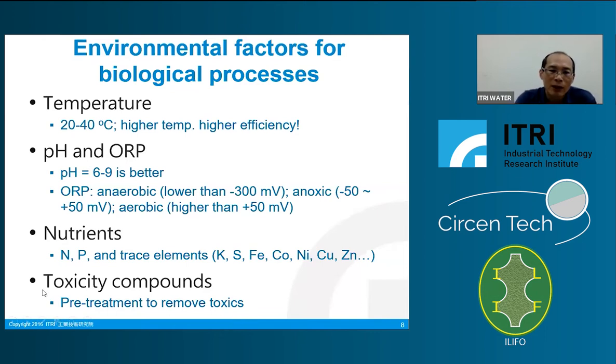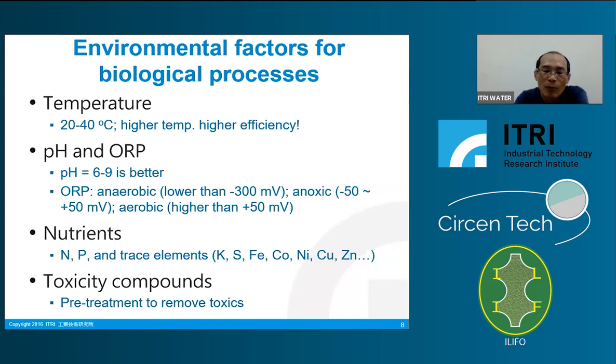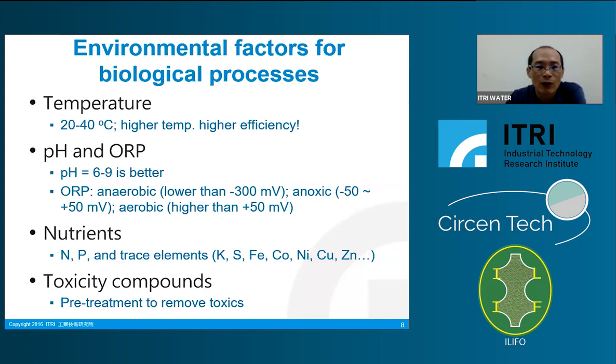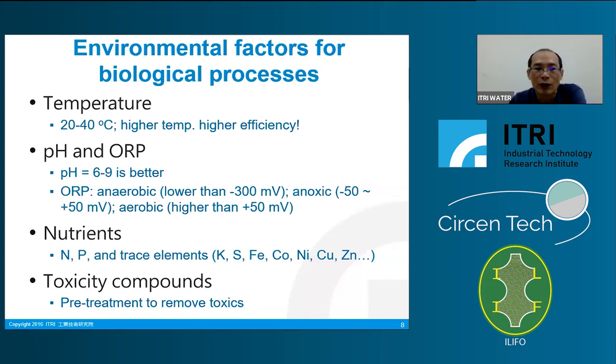The fourth factor is toxic compounds. If toxic compounds are present in wastewater, pre-treatment is needed to remove them before introducing wastewater to the biological treatment process. When these four parameters — temperature, pH/ORP, nutrients, and toxics — are within acceptable ranges, biological processes will operate well.